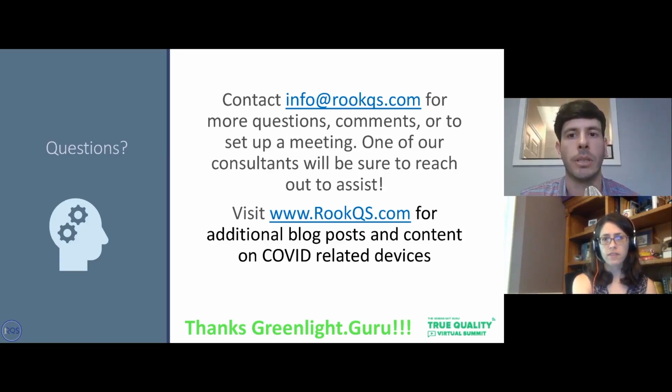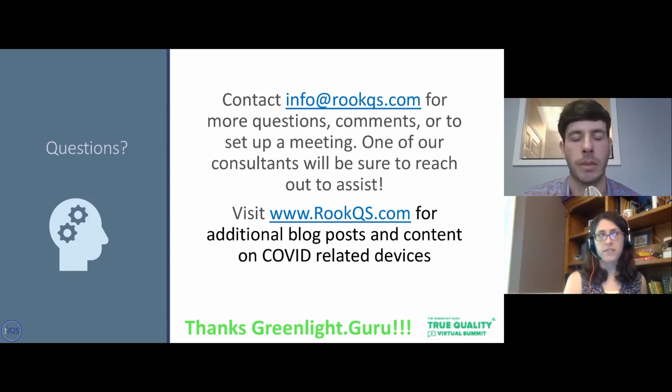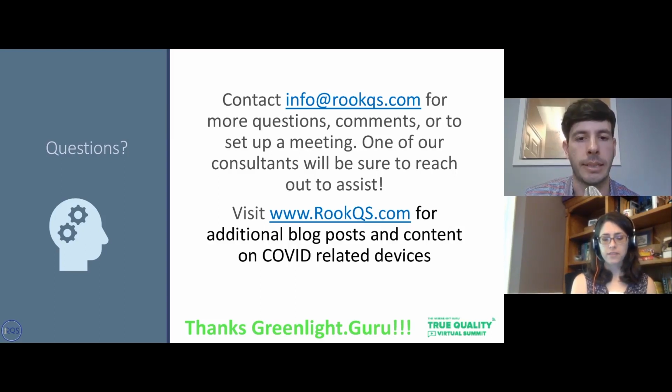Yeah, so the digital therapeutic guidance does a really good job of outlining what is required. So that's the foundation we've been using for our software related companies. I think Allison will talk about this a little more this afternoon, but they've identified your traceability matrix, which goes through your requirements, your risks, and your testing, and then your IFU and labeling, and a high level verification validation plan as the key aspects of what they would want to see. So those would also be included in your 510K, but additional information might not be required.